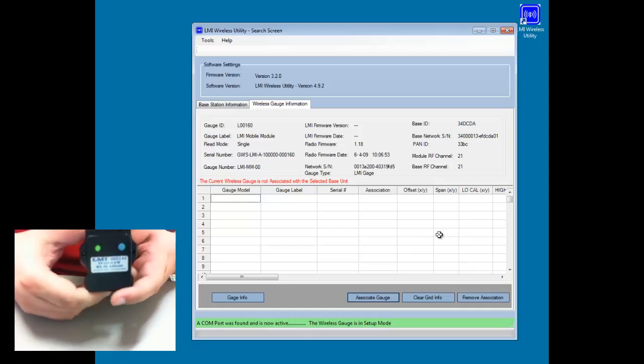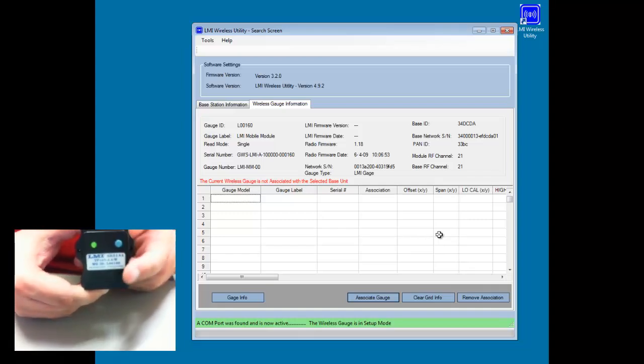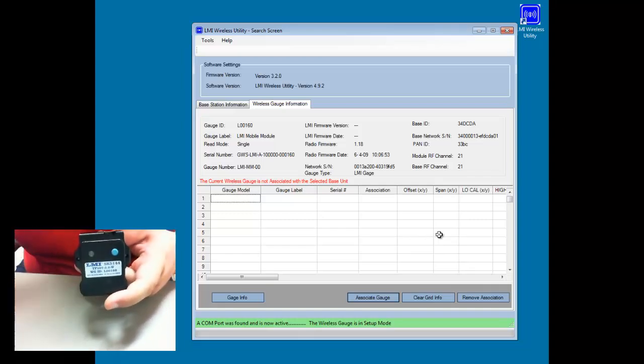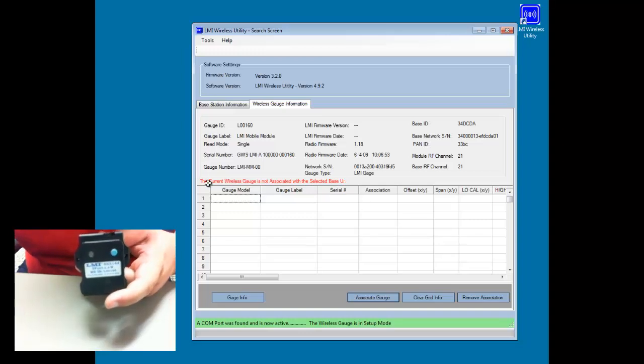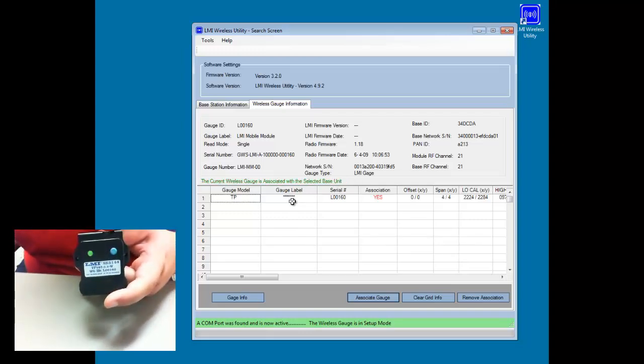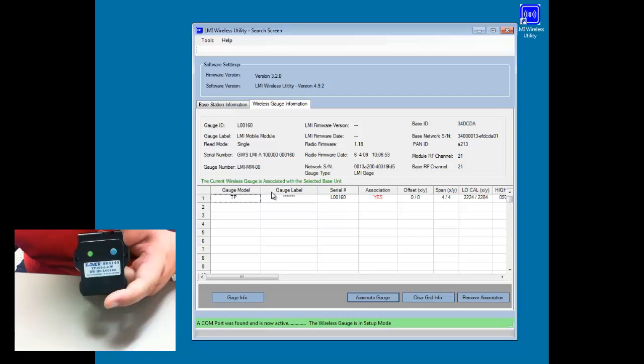Click OK. And then the last thing we're going to do is push and release the button one more time. When we do this, we should see that what's red here becomes green. And we should also see the grid populate with the gauge model, the serial number, and certain calibration info that's already stored inside this probe.